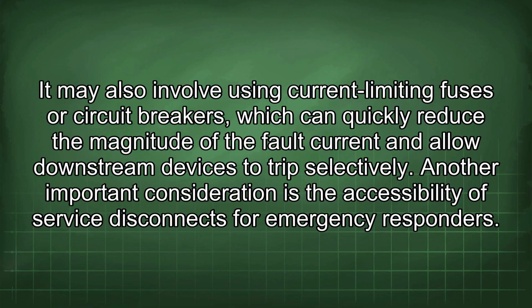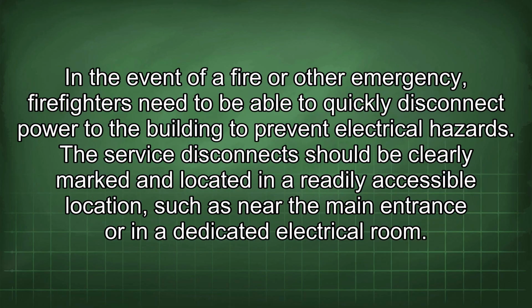Another important consideration is the accessibility of service disconnects for emergency responders. In the event of a fire or other emergency, firefighters need to be able to quickly disconnect power to the building to prevent electrical hazards. The service disconnect should be clearly marked and located in a readily accessible location, such as near the main entrance or in a dedicated electrical room.